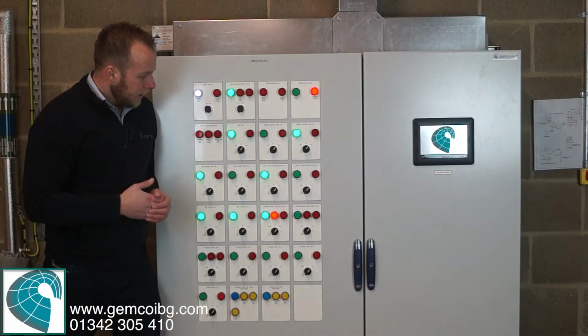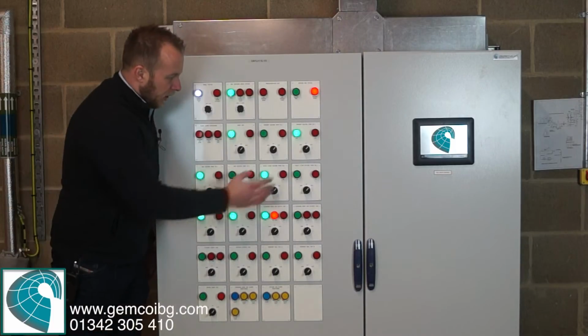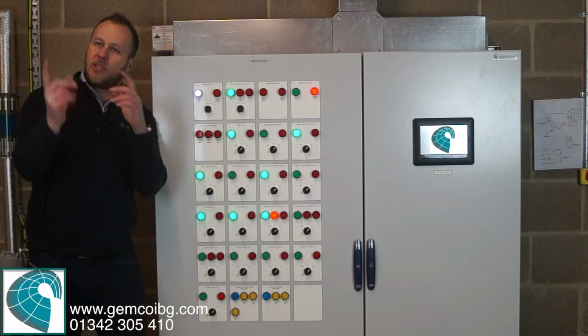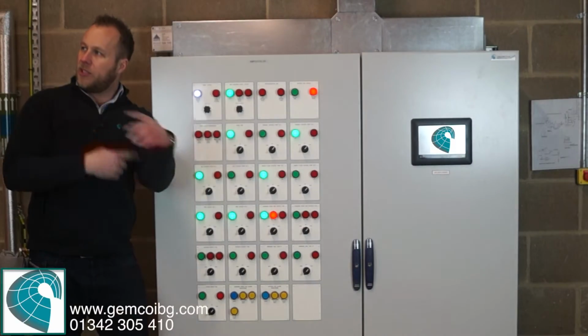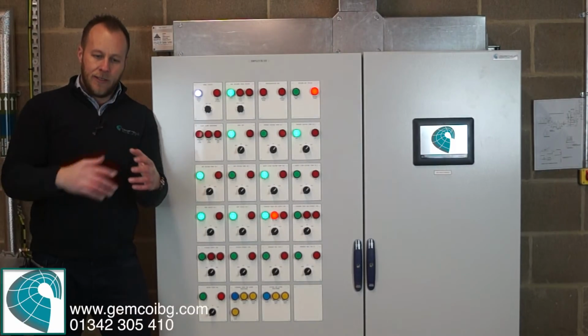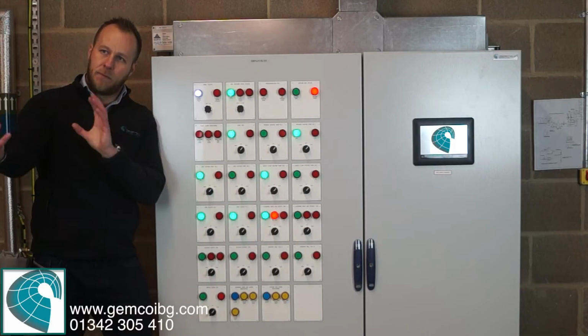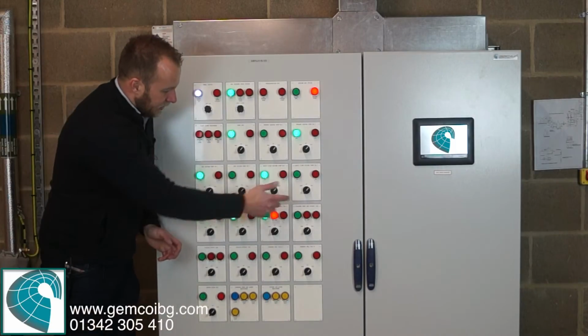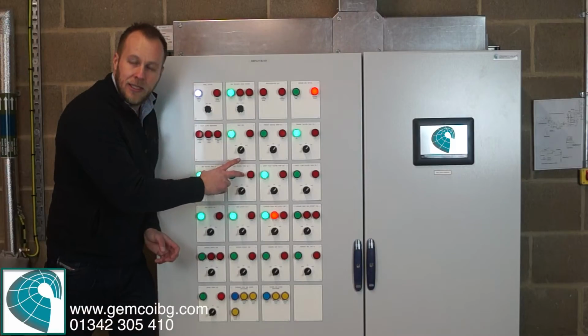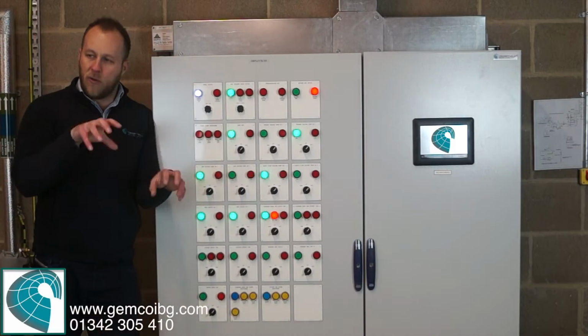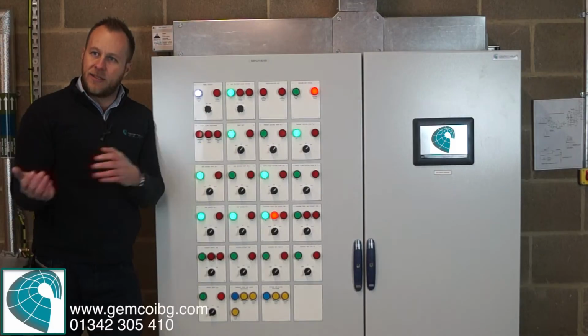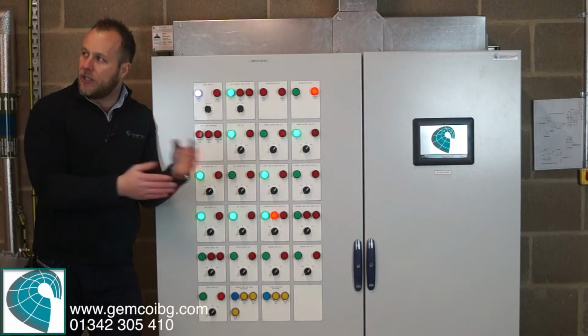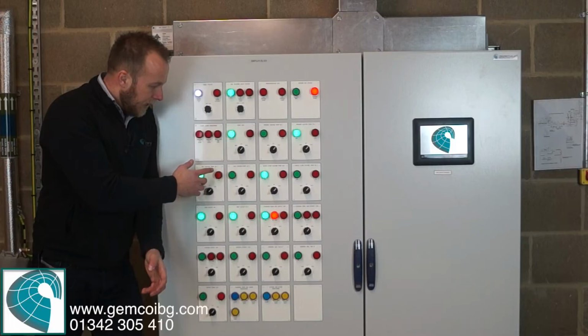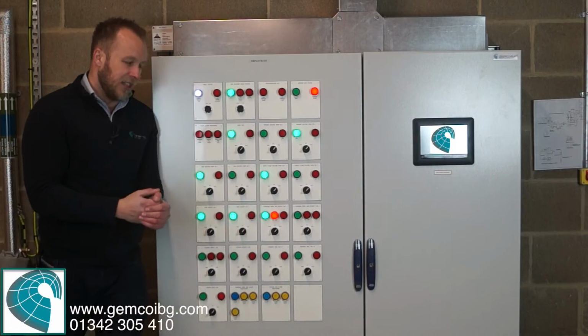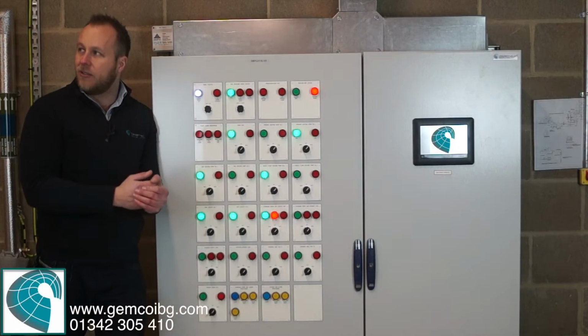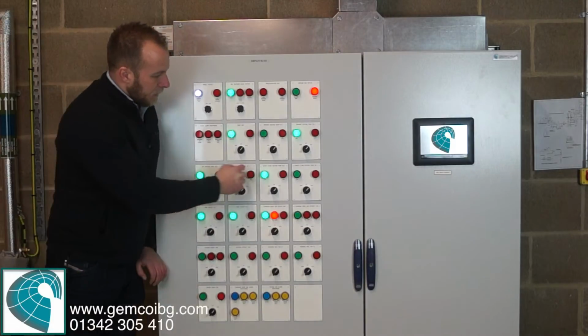So going on to pumps, you've got a primary set, which just circulates around the primary side of the plant room. Once it comes off of the boiler, we've got some pumps circulating around the plant room, and then you've got a couple of secondary sets. One does the air handling units. On each air handling unit, you've got control valves that allow certain heat to be passed to the coil so that you can temper the air to the building. And then you've got an underfloor heating circuit, which, as I said, just maintains 60 degrees all the time. Each of the pumps is a twin set.